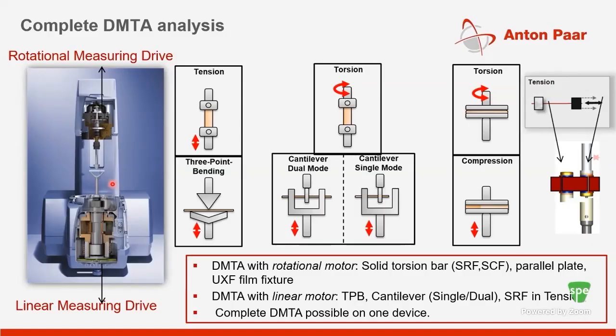Now, I've seen examples of traditional rheometers which claim that they can do some sort of axial DMA, but the challenge is most times the specs on those systems are that they can do about 50 to 100 microns in axial displacements. So this is a huge improvement in that regard, where you can do 9,000 microns, and this is actually a full-fledged DMA. And this becomes more clear when you try to characterize films and similar samples in an entire temperature range, where for the same force you need higher displacements as the material traverses through the glass transition.